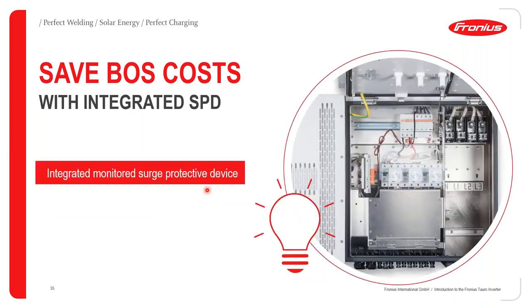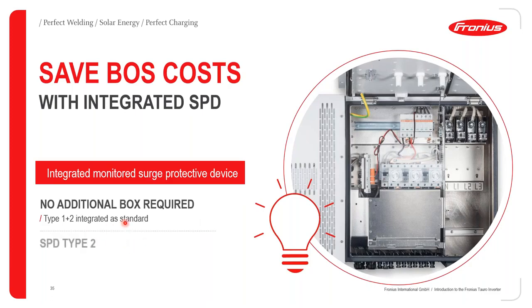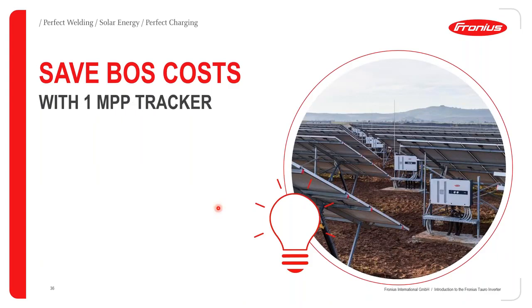As far as the SPDs are concerned, this is also something you should take note of: the SPDs that are required for protection on the DC side are already integrated into the Fronius Tauro inverter. As standard, a type 1 and 2 is integrated, and type 2 can be integrated as an option. If you require type 2 instead of type 1 and 2, you can specify that when you're making your orders. This is important because you are not going to incur additional costs when you think about SPDs for your inverter.